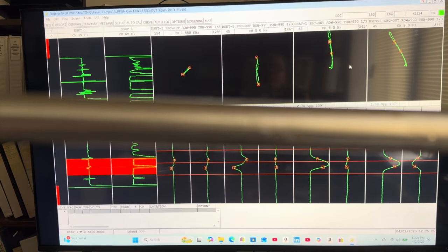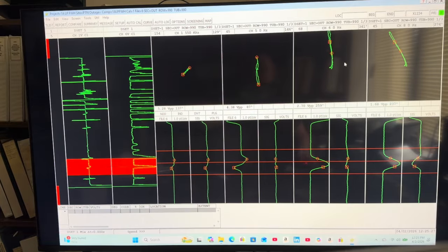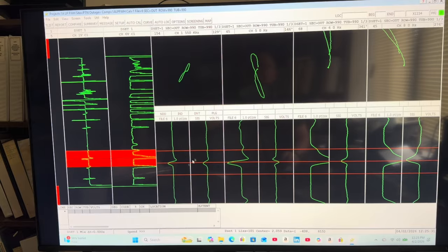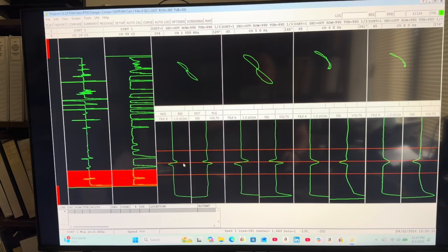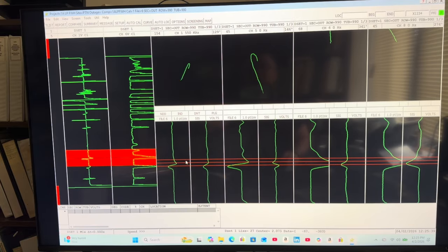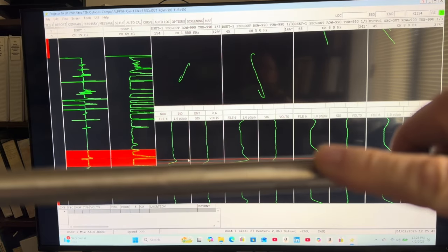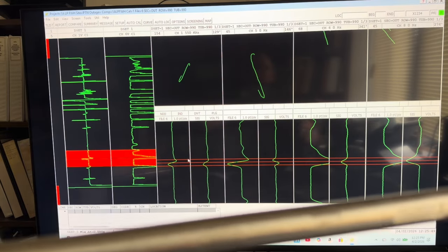Then we've got some tapered wear right here. Now notice the difference between, this is the hole, it's got some certain axial length to it here. And when we get up to this guy, it's a little bit wider. That's because these two flaws that I introduced have a little bit of width to them.